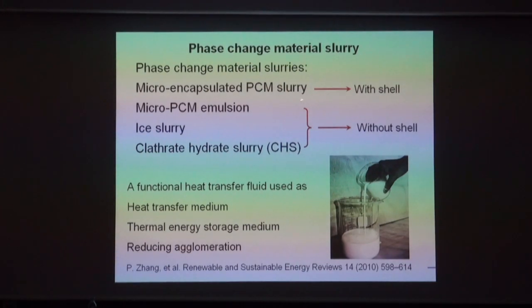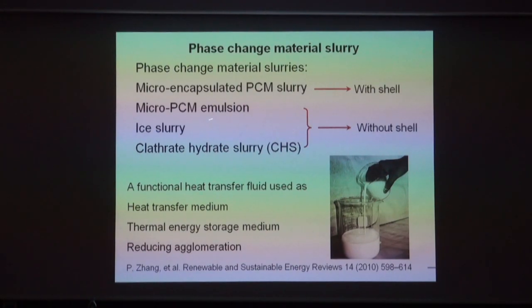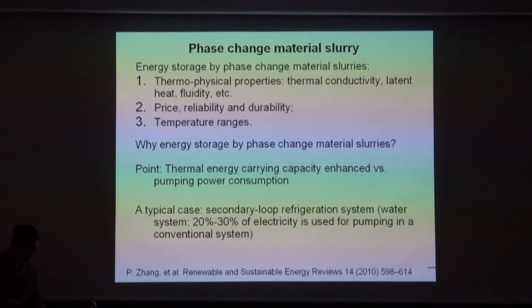In general, there are four kinds of phase change material slurries. With a shell, it is micro-encapsulated PCM slurry. Without a shell, there are three kinds: micro-PCM emulsion, ice slurry, and clathrate hydrate slurry—CHS for short. The reason to use PCM slurry for energy storage is that the thermal energy carrying capacity versus pumping power can be largely enhanced compared to conventional water systems, where 20–30% of electricity is used for pumping.